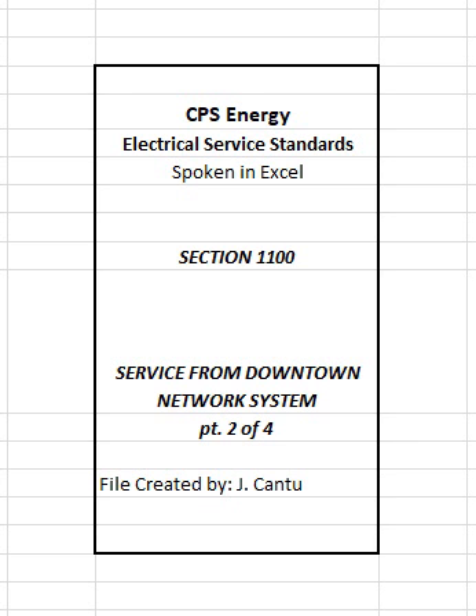All sealant used inside the transformer vault or room shall be UL approved. 5. A separate 2-inch pipe to city storm drainage system will be required. Customer shall coordinate with the CPS Energy customer service representative.